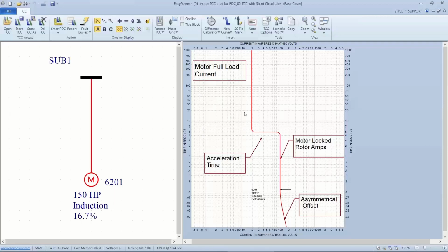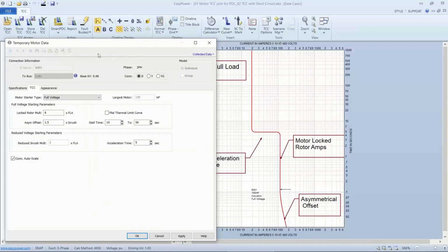The characteristic chair shape is built upon the full load current being the top vertical section. So any time current plot to the left of the red chair would be considered a normal start. The horizontal length of this line between the locked rotor amps and the full load current is referred to as the acceleration time. And then this tail is the asymmetric offset. When we first energize, it's somewhat similar to the inrush. Now, all this is related to the setup that we used on the TCC plots for the motor itself.